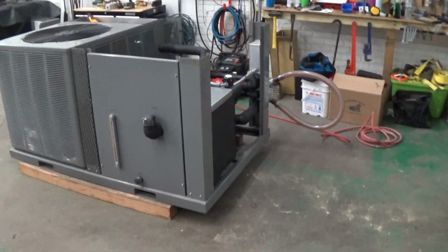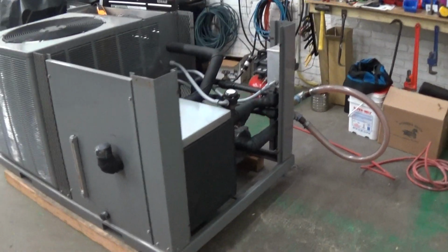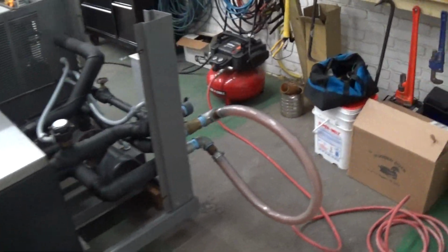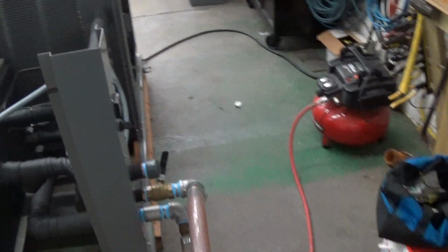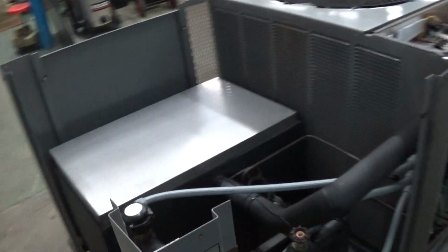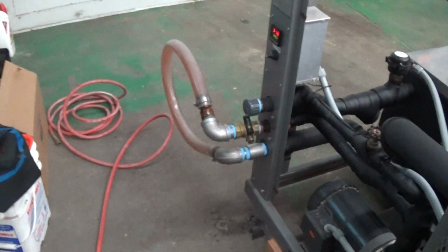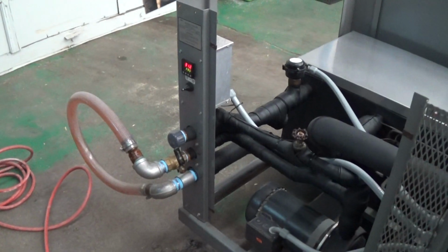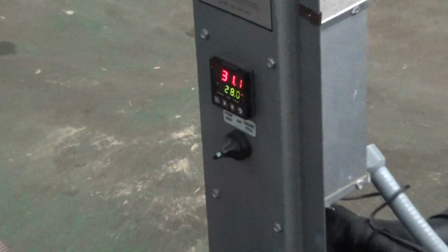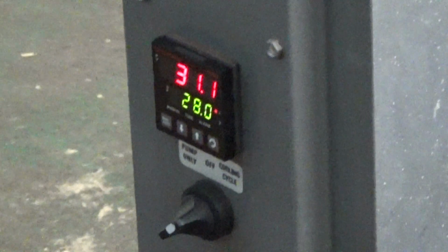This is our video number 3 on this 7.5 ton cold shot. What I actually chose to do this time is, since video number 1 and 2, I just left the unit running for about 3 days because it's over a weekend. And the way the controller works here, our minimum set point's 28.